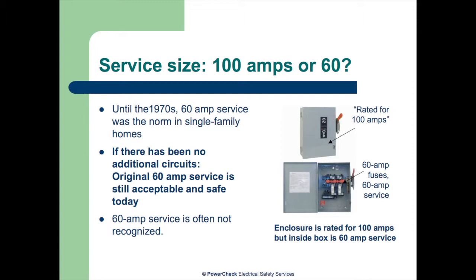60 amp service was the norm in house wiring until the 70s. And then in the 1970s, because of the potential of basement suites and the potential of more heating demand, which was electric ranges, electric dryers, and baseboard heaters, for the potential of those extra things that were going to be needed due to multiple suites, the Canadian Electrical Code said for all new houses greater than 80 square meters of living area, we're going to have a minimum of 100 amp service.